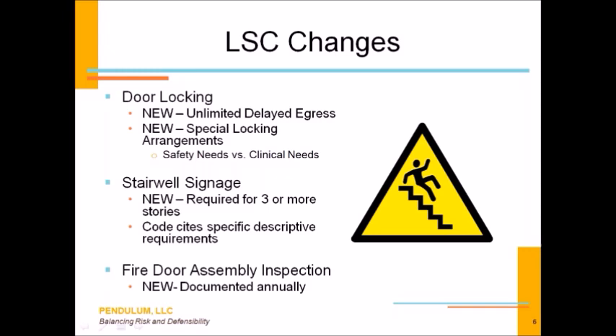When it comes to special locking arrangements, previously the code would only factor in the clinical needs of your patients or residents, allowing you to have secure facilities with certain types of locking arrangements. The newer edition of the code, the 2012 edition, allows you to factor in the safety needs of the residents. So it's kind of a broader interpretation. You really need to get into the NFPA 101 handbook and the code itself to look at those types of conditions that allowed for special locking arrangements. But in the context of our call today, I just want you to know that you've got a broader application of having a locked facility.